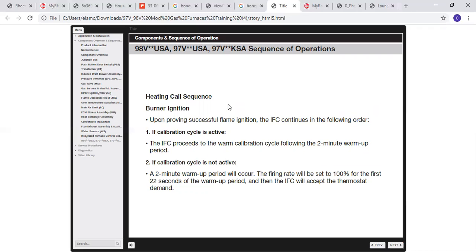So the heating call sequence: upon proving successful flame, the IFC continues in this order. If the calibration cycle is active, the IFC proceeds to the warm calibration cycle following the 2-minute warm-up period. If the calibration cycle is not active, a 2-minute warm-up period will occur. The firing rate will be set at 100% for the first 22 seconds of the warm-up period, and then the IFC will accept the thermostat demand.